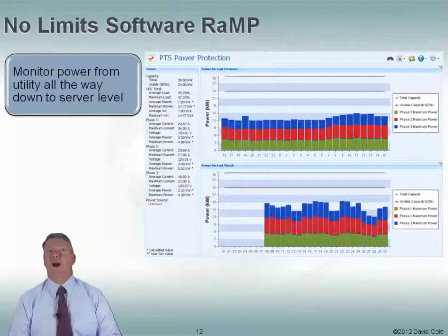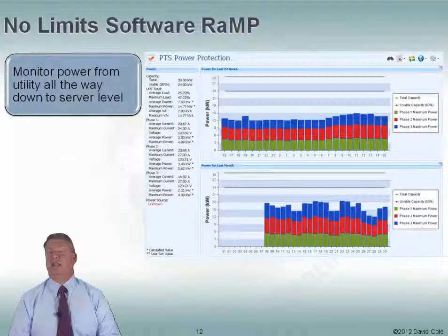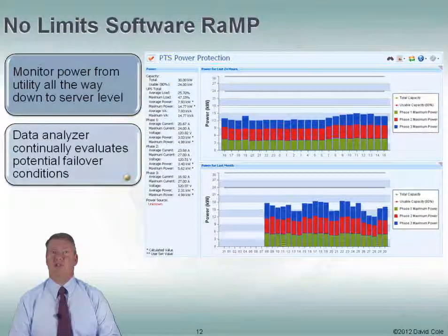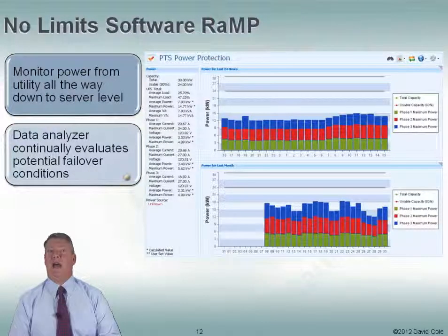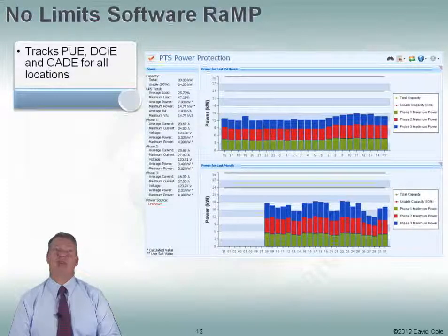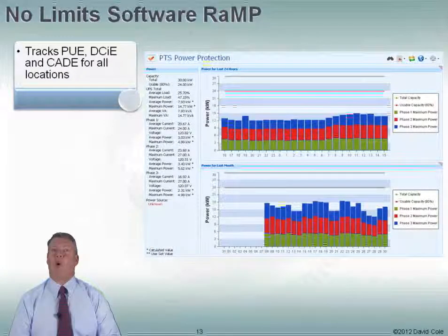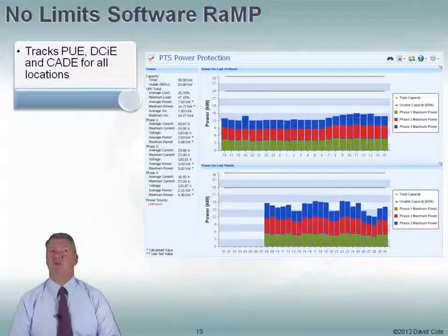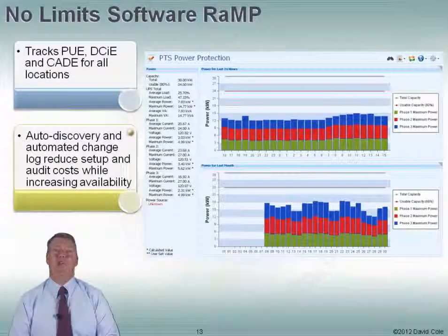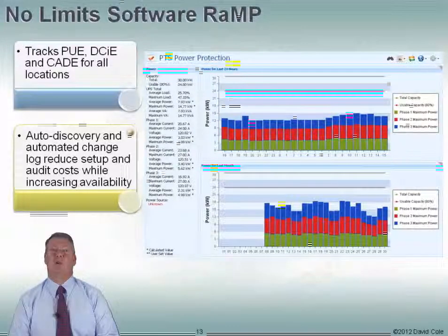No Limits Software RAMP monitors power all the way from the utility down to the server level — it will go down and talk to individual IT devices, which is a little different than some products. It has a data analyzer that runs in the background and continually evaluates potential failover conditions, so if a rack PDU were to fail, you'd know what impact that would have. It tracks PUE (power usage effectiveness), DCIE (data center infrastructure efficiency), and CADE (corporate average datacenter efficiency) for all locations. Because it monitors all the way down to CPU usage, it can track CADE, which takes into account IT efficiency. It supports auto discovery and automatic change logging, which reduces setup and audit costs and increases availability.